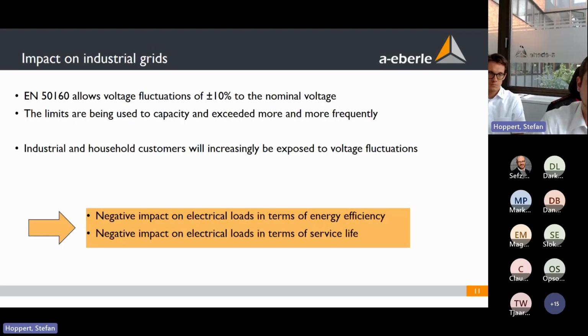And what's the impact on the industrial grids? Up to this point, I just spoke about the impacts on utility grids. But industrial customers are connected directly to the utilities, and the utilities are allowed to supply industrial customers with plus minus 10% of the nominal voltage. That's the standard EN 50160, a European standard. It is also fulfilled worldwide, but in many countries it is not just plus minus 10%. Very often plus minus 20% is the case.